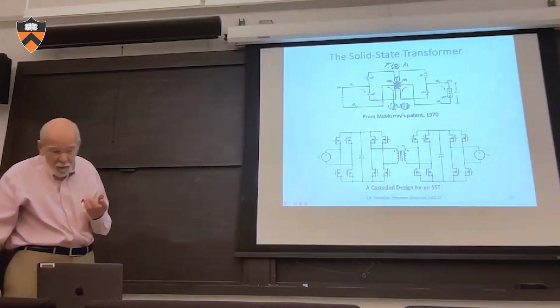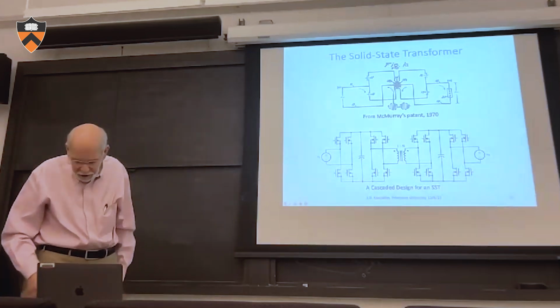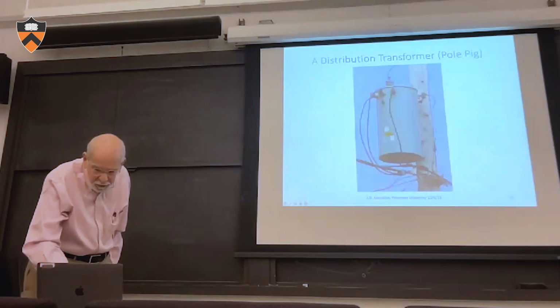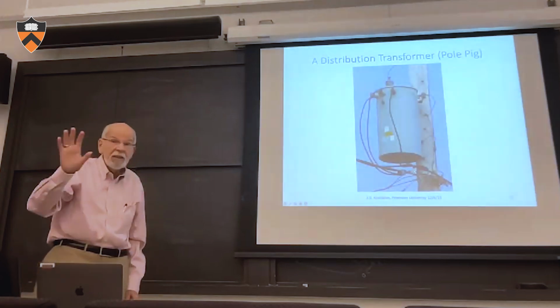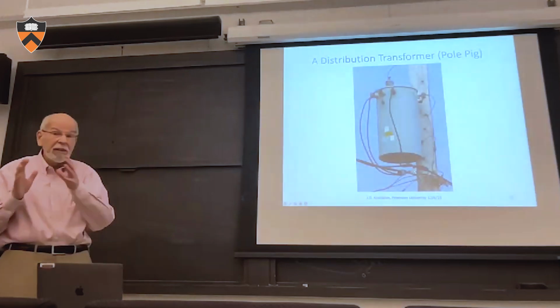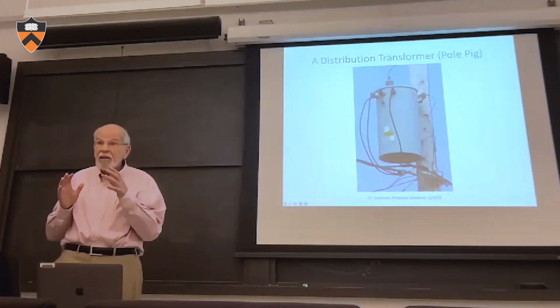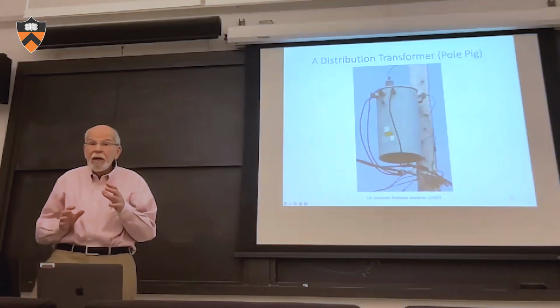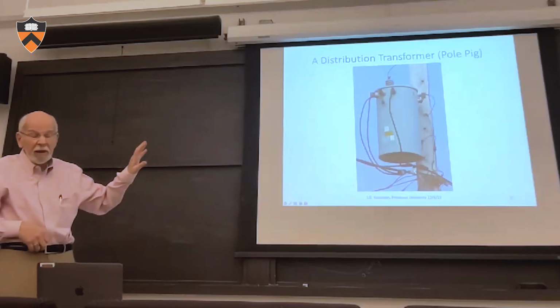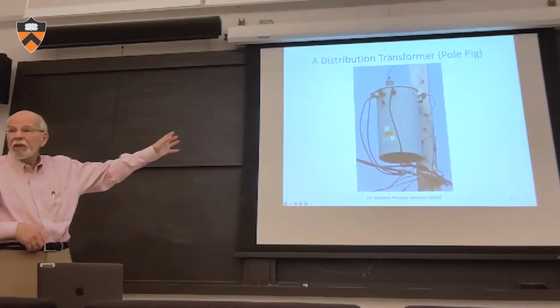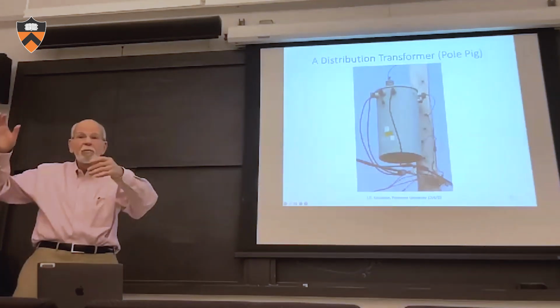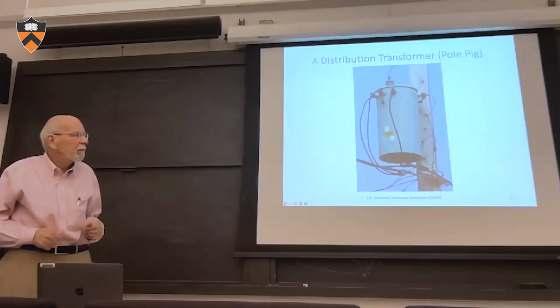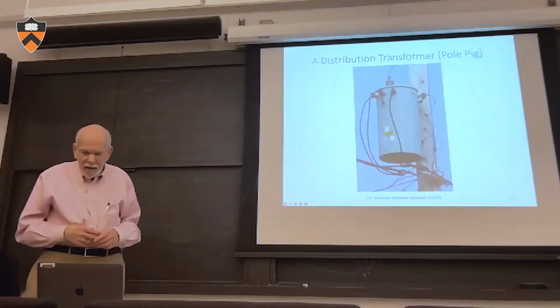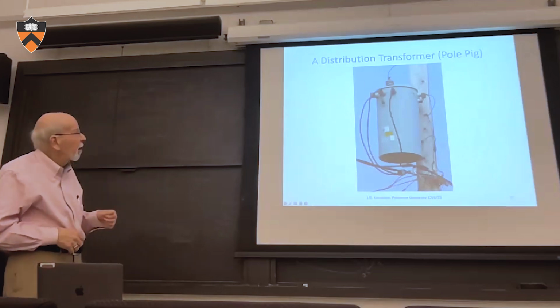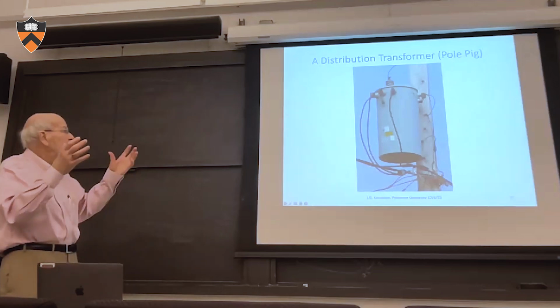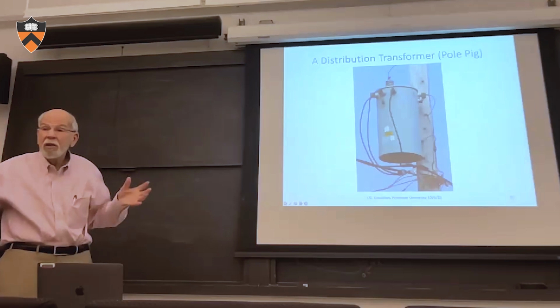So what's the deal with this? Well, this is my opinion about the best application for the solid state transformer: to replace the pole pig. Now, the pole pig is a distribution transformer that you see on telephone poles, power poles, basically oil filled. It's running all the time.